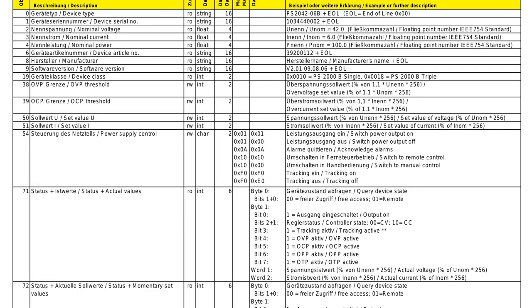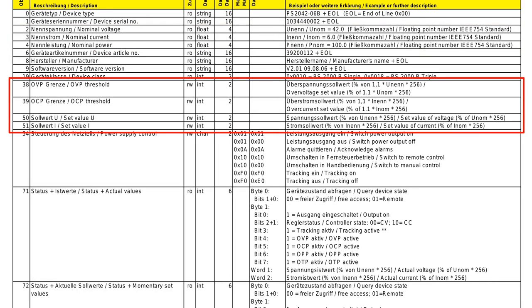First, what is weird is how you get the values. There are several ways you get the values. Here you can use this object to get the nominal voltage, nominal current, nominal power, and then it sends a float, and this float is encoded using the IEEE 754 standard as defined here. And then there's another way to set and read the value, which is defined here, where you send an integer - actually a 2-byte integer - and it's the percentage of the nominal value times 256 times 1.1.